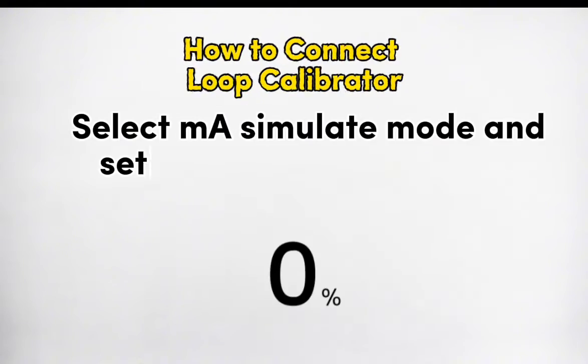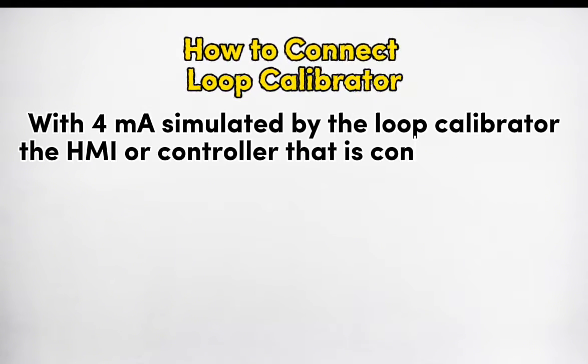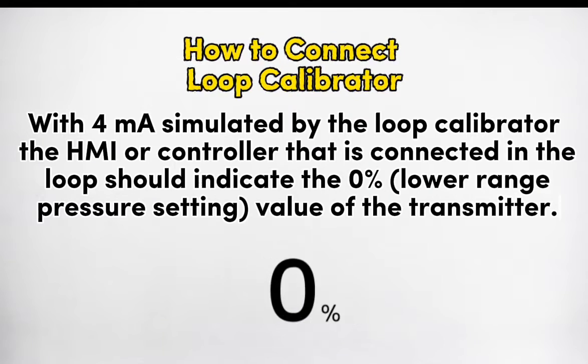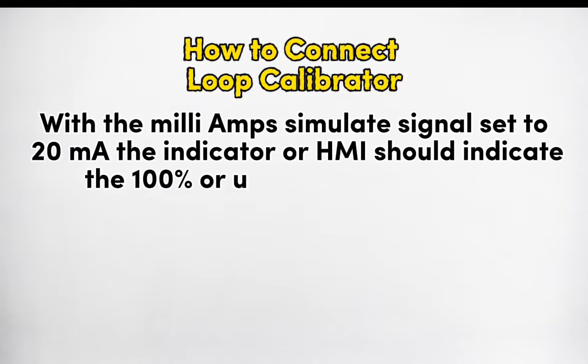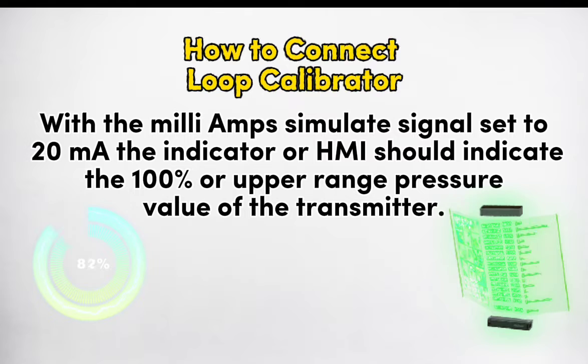Select milliamp simulate mode and set the loop calibrator to a milliamp signal value. With 4 mA simulated by the loop calibrator, the HMI or controller connected in the loop should indicate the 0% lower range pressure value of the transmitter. With the simulate signal set to 20 mA, the indicator or HMI should indicate the 100% upper range pressure value of the transmitter.